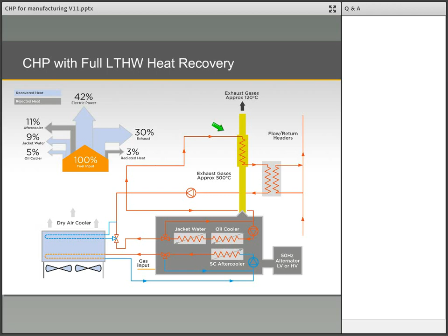Heat recovery from CHP is not an either-or situation. If there is a fluctuation in the site heat requirement and it can no longer utilise all the heat produced from the CHP, the control system will detect a rise in return temperature and start to divert some of the return flow to the radiator via the 3-port valve, where an element of the heat will be rejected to atmosphere. If the return temperature continues to rise, the system will increase the flow to the radiator until either the return temperature stabilises or all the heat is being rejected.